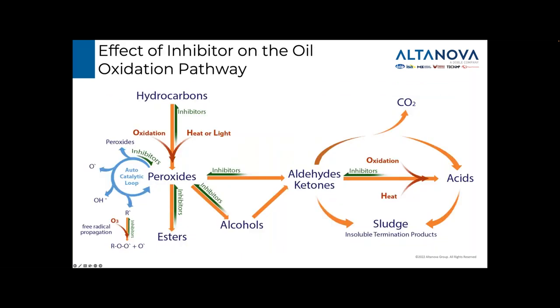So on to inhibitors. As oil ages, it causes reactions in the oil to darken it in appearance, and the oil eventually becomes sludgy towards the end of its life. This sludge is like cholesterol in our blood vessels.